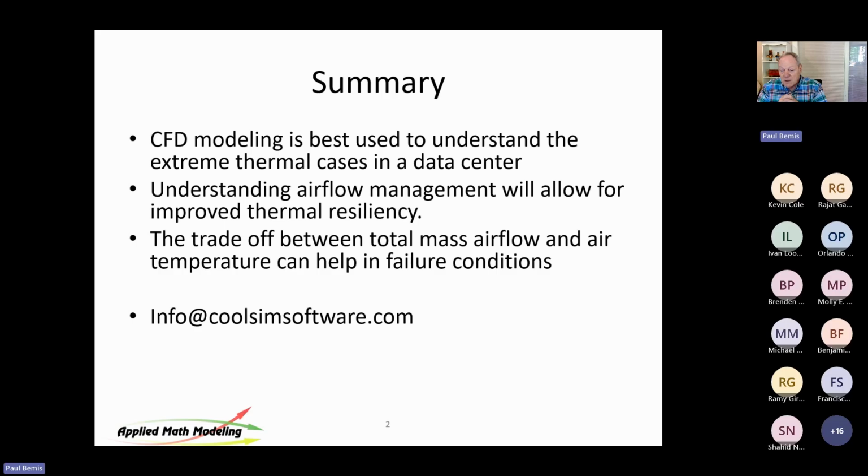And I'm assuming you're talking about local outdoor climate. So I'll give you an example. I was working on a data center not too long ago where the customer thought that the walls were leaking because they had added up mathematically the cooling capacity they had, and they certainly had enough cooling capacity, yet on hot days, they weren't able to cool their data center.